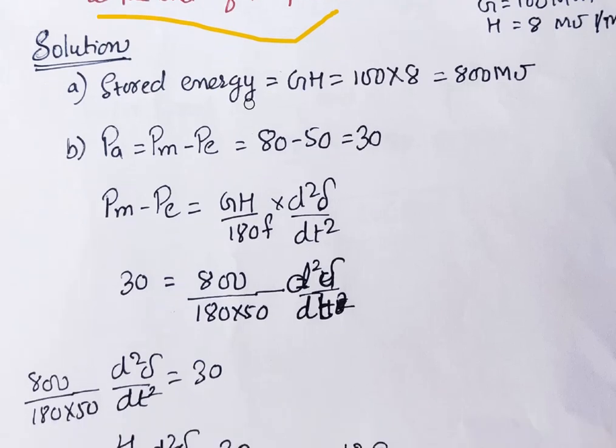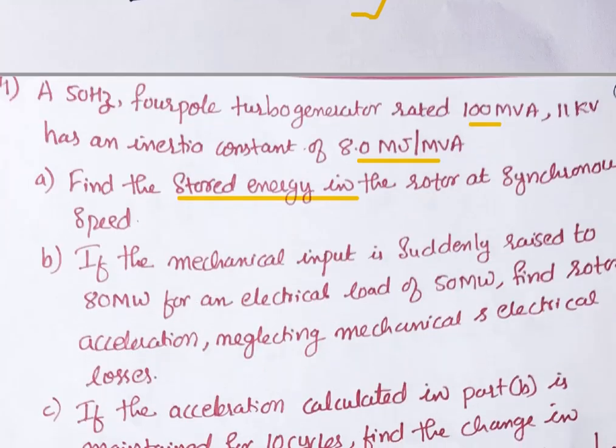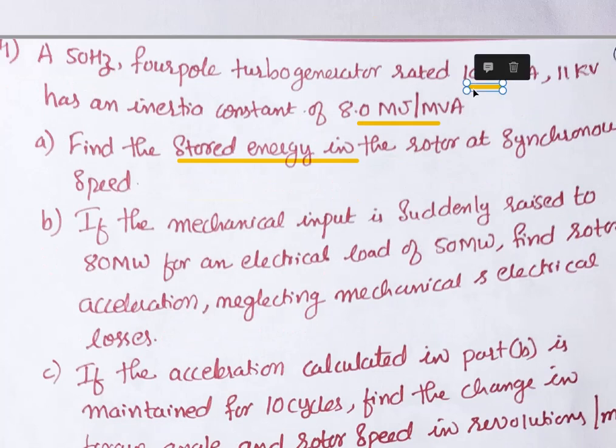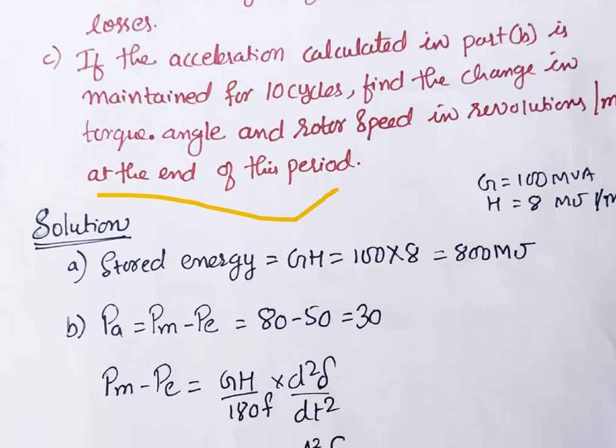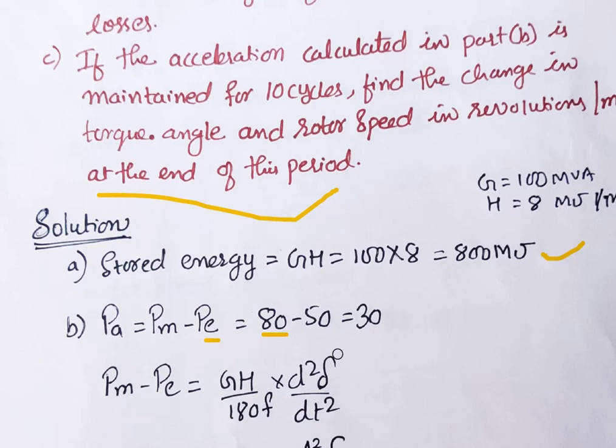The stored kinetic energy = G × H = 100 × 8 = 800 megajoules. Due to the disturbance, mechanical power (driving force) = 80 MW and electrical power (opposing force) = 50 MW. The net accelerating power = 80 − 50 = 30 MW, which is positive since the driving force exceeds the opposing force.